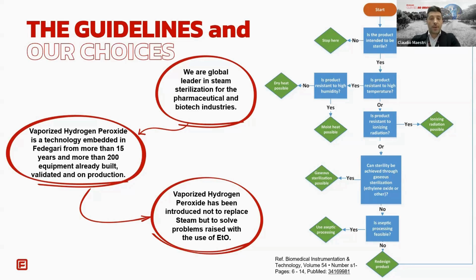When selecting a sterilization method, it's not just about killing microbes. We have to protect the essential quality attributes of the material, and we must achieve sterility assurance levels that meet or exceed regulatory expectation. Some key considerations include, first, intended use. We need to understand how the device interacts with a patient, which directly defines if sterilization is required. For instance, devices contacting the bloodstream or other sterile areas of the body, of course, require sterilization, while those merely touching uncompromised skin may only need validated cleaning and disinfection.